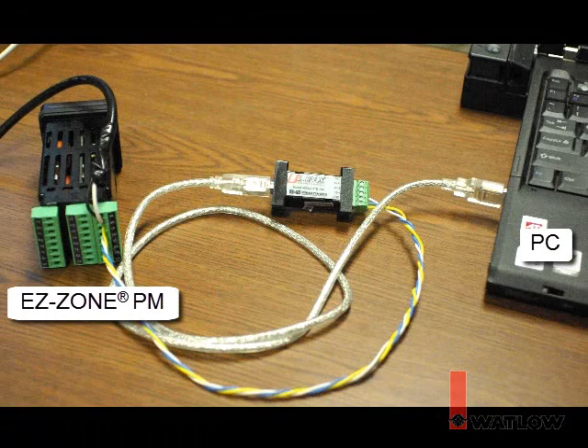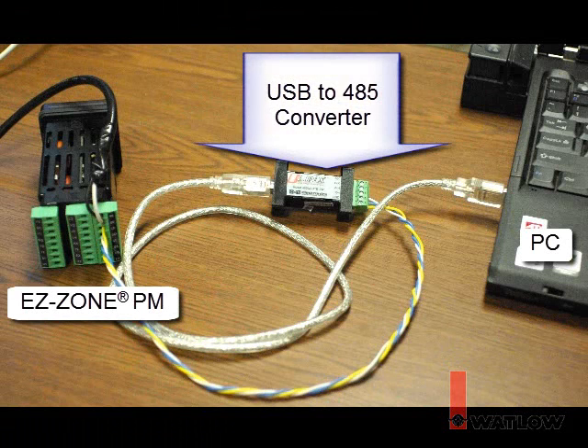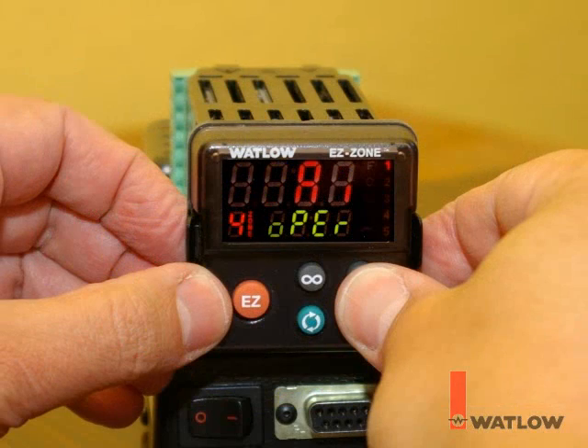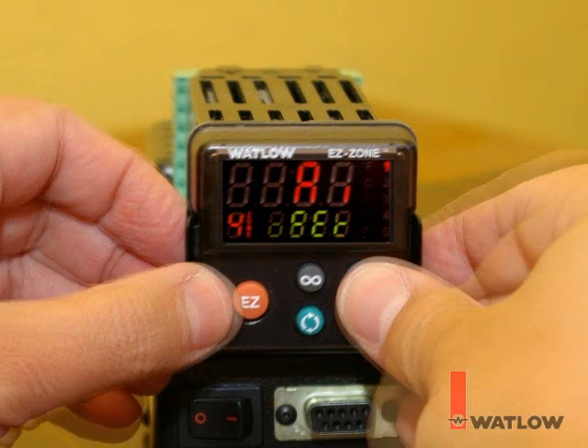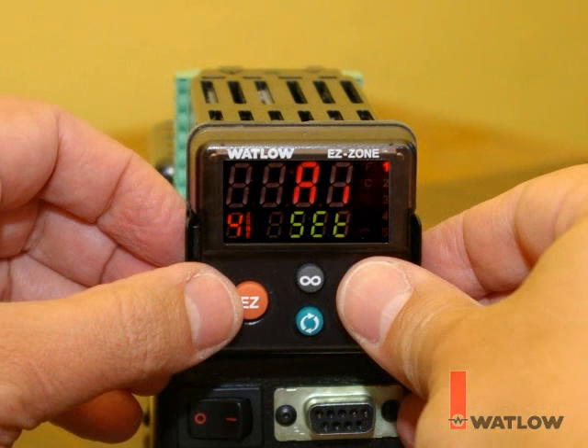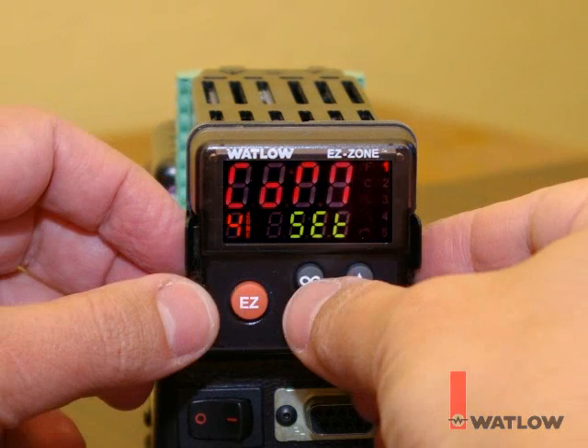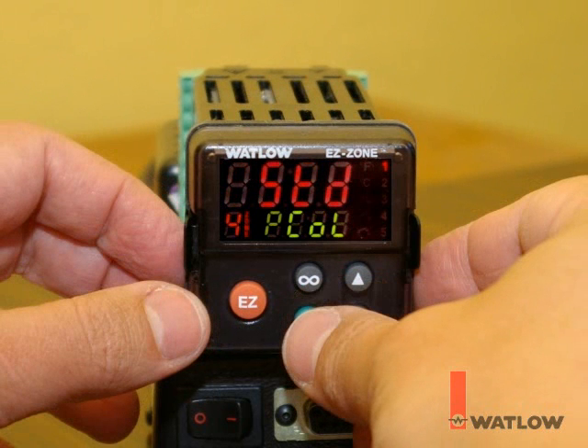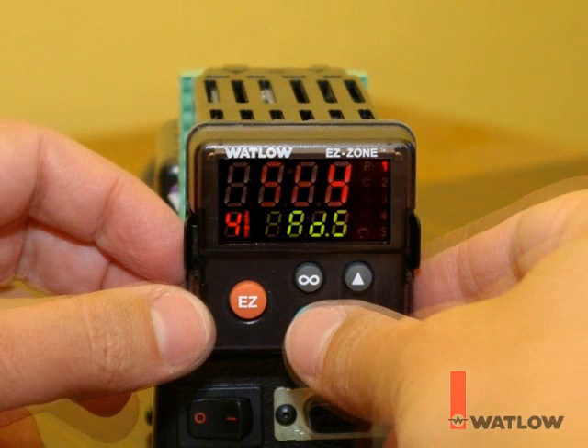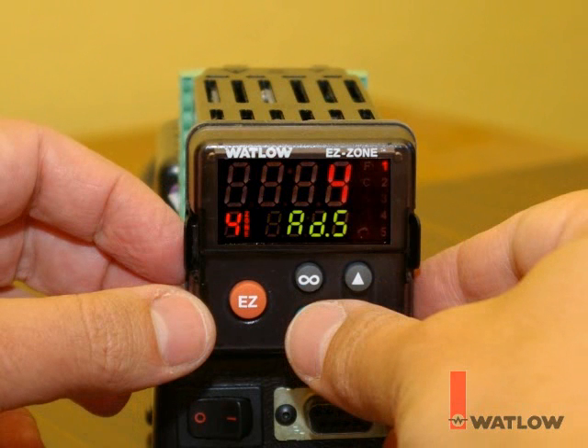In this session, the computer is connected to an EZ-ZONE PM controller via a USB to 485 converter. The converter has been installed as a serial port named COM6. Like all EZ-ZONE products, the PM supports the standard bus communications protocol. This model also supports Modbus RTU, so on the Setup Page's Communications menu, I've made sure the protocol is set to standard bus. Also, the PM standard bus address or zone number is 4.